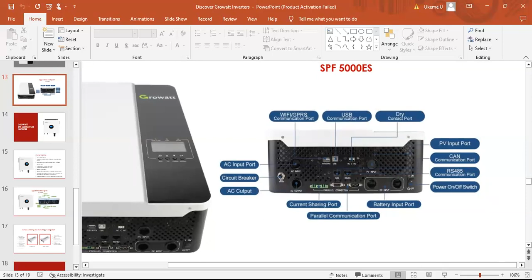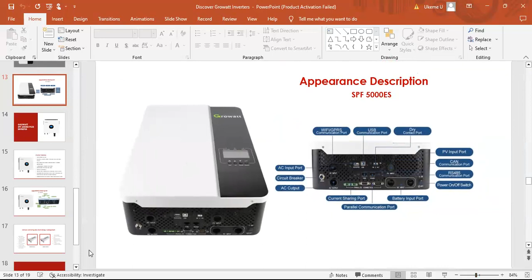Current sharing cable is needed in case you connect the system in parallel, but if the system is being run as a single unit, there won't be need to connect this current sharing cable. It's only used when you connect system in parallel. And then you have the parallel communication port. These two ports allow you to connect the system in parallel with the other inverters. Then we have the battery input ports for this one. Battery connection, negative and the positive terminal of the battery comes to this port. So this is all for SPF 5000 ES.